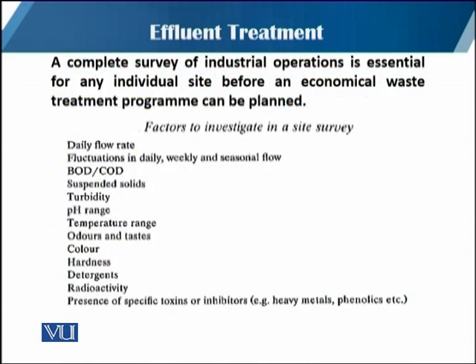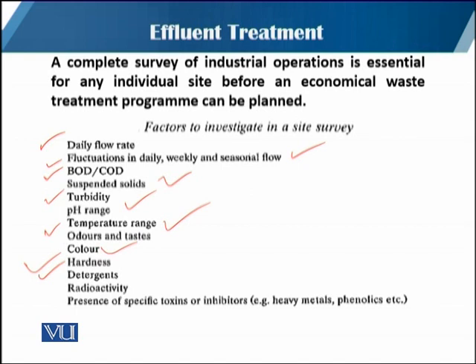A complete survey of the industrial operation is essential for an individual site before an economical waste treatment program can be planned. The factors to investigate in a site survey include: daily flow rate, fluctuations in daily, weekly, and seasonal flow, BOD and COD ratio changes, suspended solids, turbidity, pH range, temperature of the effluent, odor and taste, color, hardness, detergents, radioactivity, presence of specific toxins and inhibitors, and heavy metals and phenolic compounds.